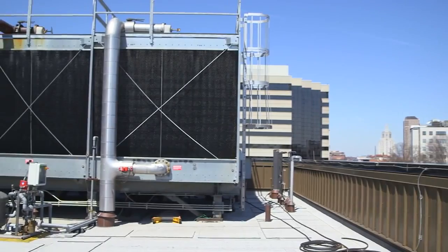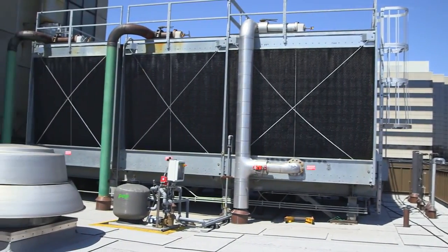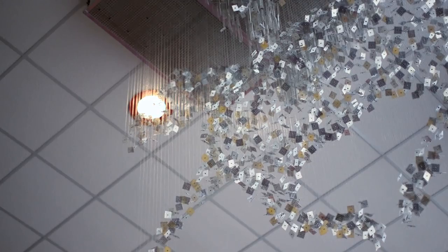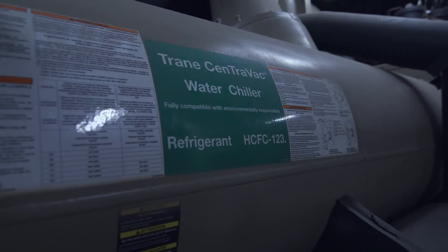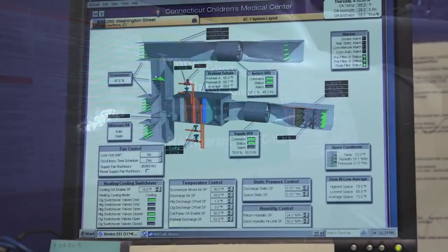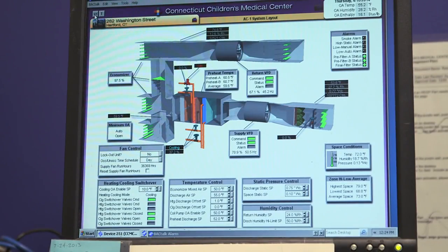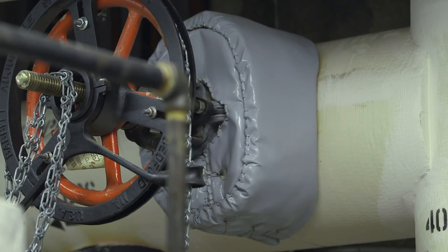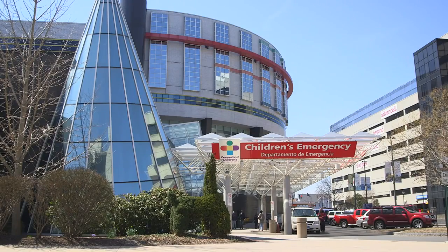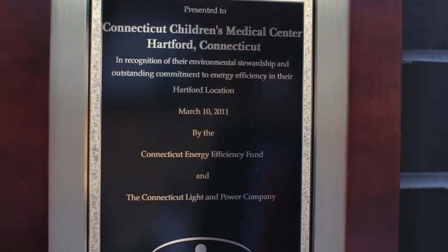We started off a few years back with a free cooling system where we use the outside cold air in the wintertime to chill the chilled water we need to cool the building and the MRI. Then we looked at sensors to turn off lights when they weren't in use, did some lighting upgrades, and added a new energy efficient chiller. We added VAVs, variable air volume boxes, to reduce airflow in areas that close on weekends and at night. We also insulated pipes and tried to make the building envelope more sealed up, and we continue to look for more things every day.